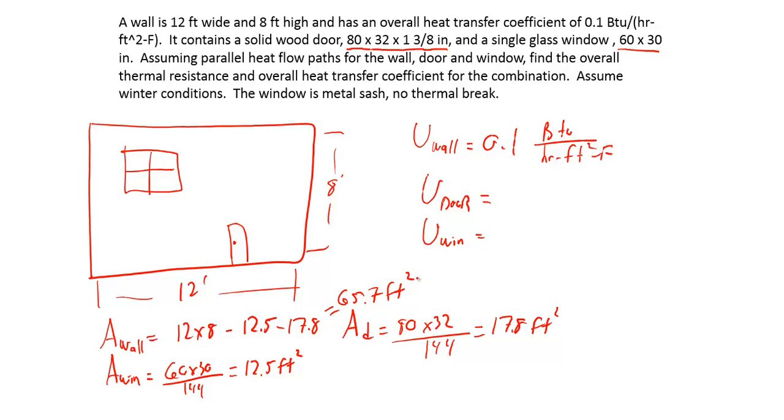Moving on from that, Table 5-8 gives you the thermal coefficients of doors. In this case, it's a wooden door, solid wooden door measured at 80 by 32. You can go ahead and see the tables and find that relatively simply. It's 1-3/8 inch thick, so a solid door 1-3/8 should give you 0.39 BTU per hour foot squared Fahrenheit.